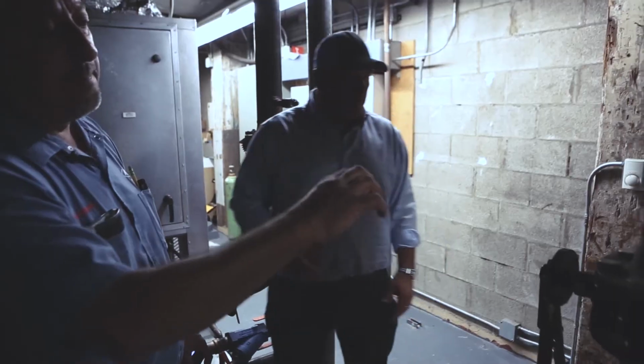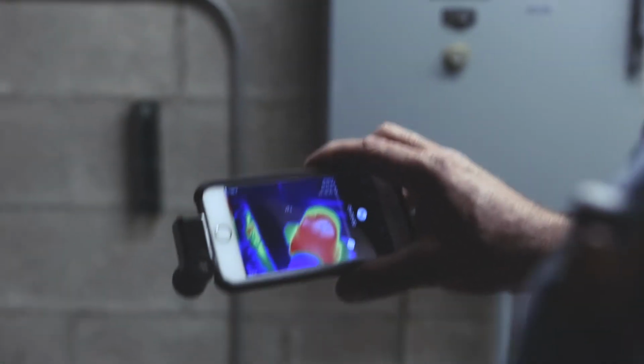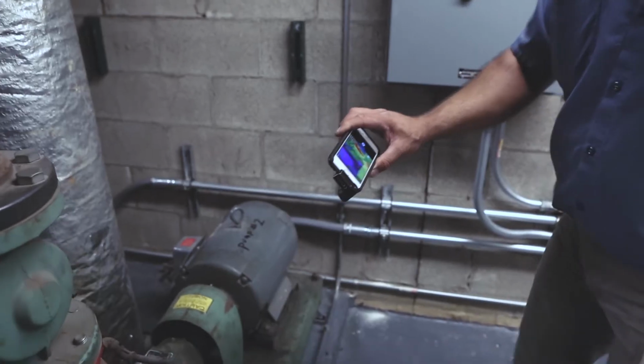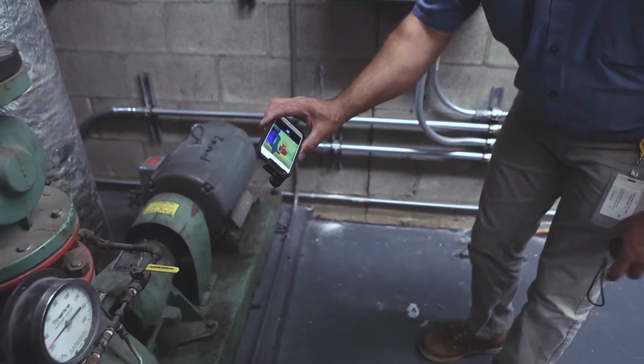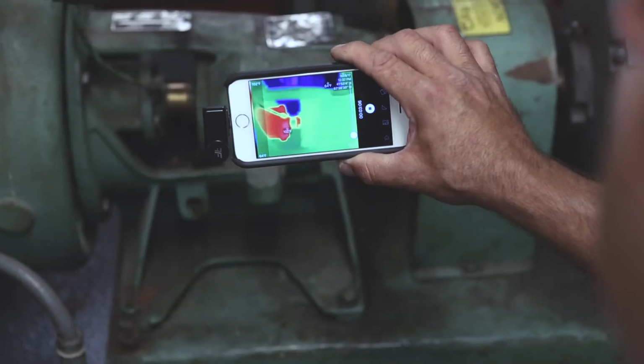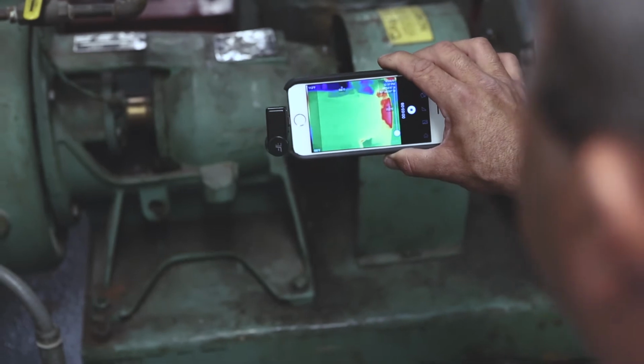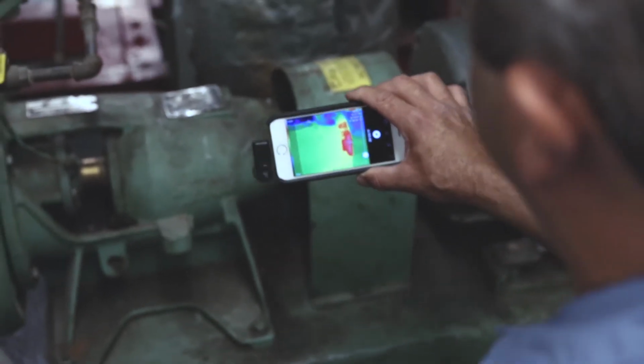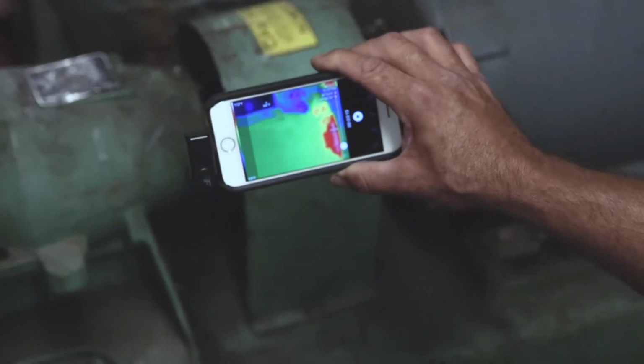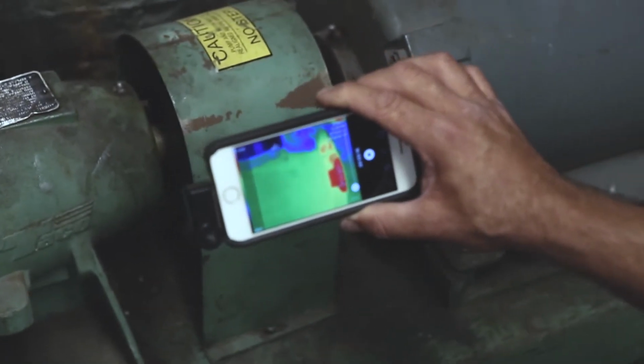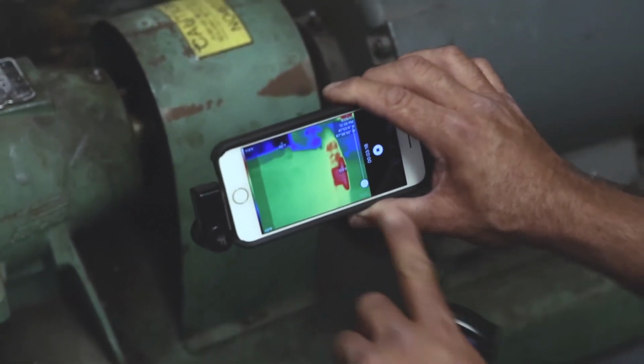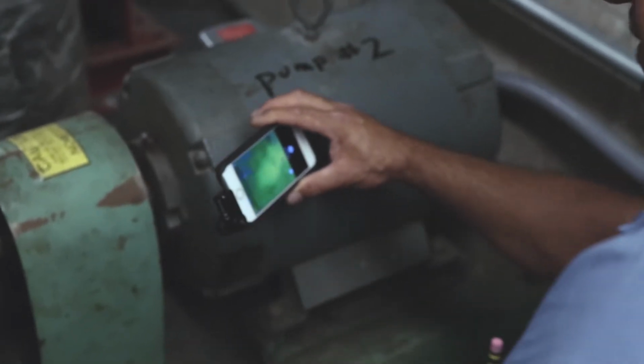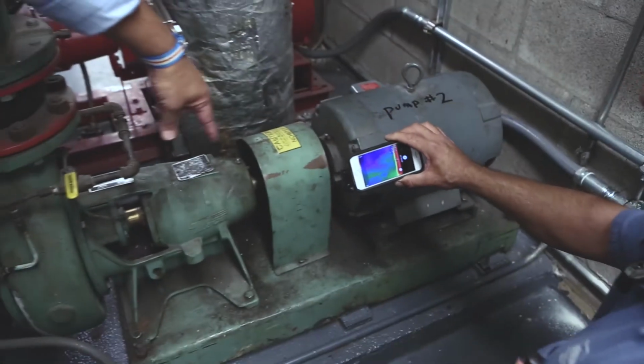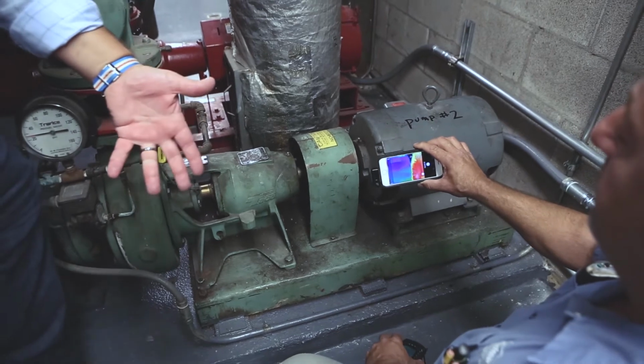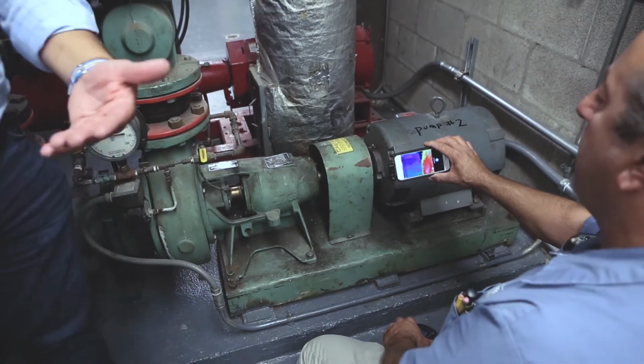Here's a scan of some pumps, my pump system. I'm going to walk over by the motor. Here's your motor that's actually in use right now. Here's my pump bearing assembly. 102 degrees there. We have 113 degrees by the coupler. This will tell you if you have a misaligned coupler. If you have misalignment on your coupler, you'll have high readings on your temps here. So if you had a misaligned coupler, you'd get the high readings on both sides, yes, probably. Yes. One is probably right, but if you had both sides, that means that you're out of alignment.